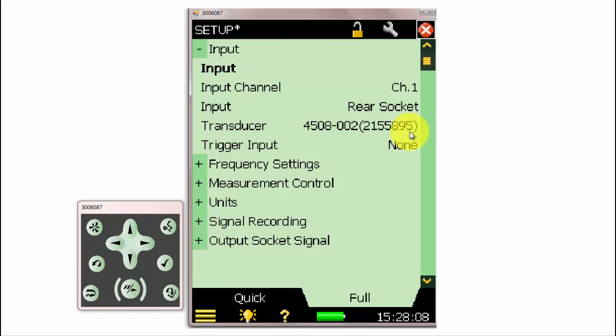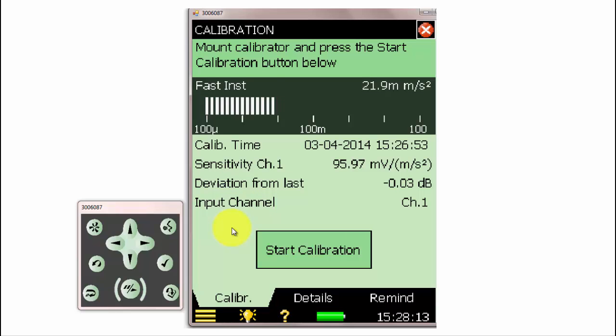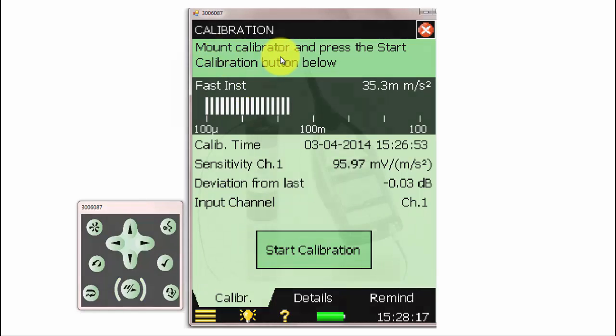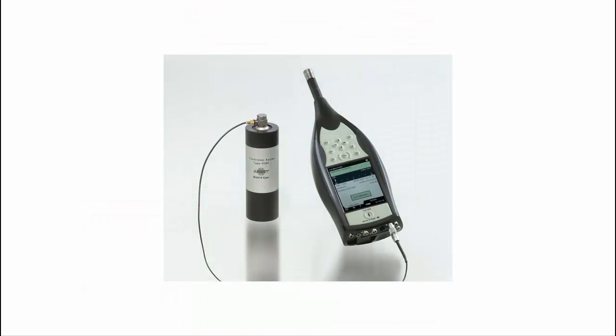Next, we can go to the main menu and go to Calibration. We first mount the accelerometer on the calibrator and press Start. Back on the meter, we can press Start Calibration, and the meter will perform a calibration measurement.